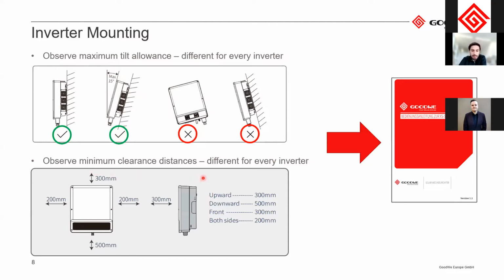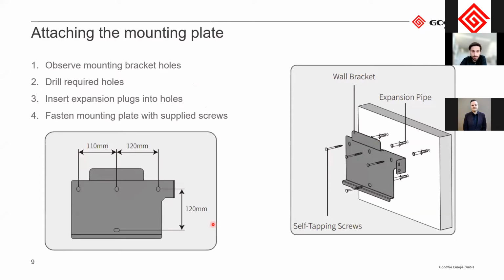Please also observe the minimum clearance distances, and this also differs for each inverter. Here you see for the ET, you have roughly 20 centimeters to the right and left or to the sides, and then 30 centimeters upwards and 50 decimeters, 5 decimeters, sorry, downwards. When attaching the mounting plate, observe all mounting plates also look different depending on the inverter. Observe the holes, and then you just drill the holes and attach. Make sure that this one is properly attached before you then hang the inverter on, and use these holes on the side to fasten the inverter to the mounting plate.